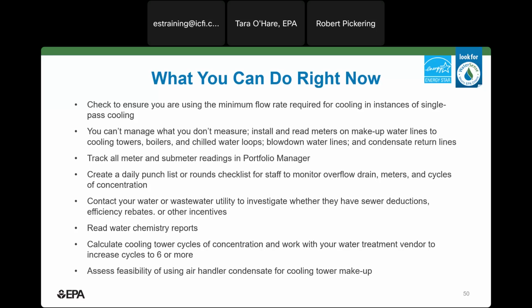Create a daily punch list or rounds checklist for assigned staff to monitor the overflow drain, meters, and cycles of concentration to make sure that the cooling tower is operating correctly. As I mentioned, doing these three things can really prevent a lot of water waste that occurs from a malfunction or mechanical issue that arises. Next, contact your utilities to see if they have any programs that could help you save water and money. This includes the sewer deduction credits, rebates, or assessment support.